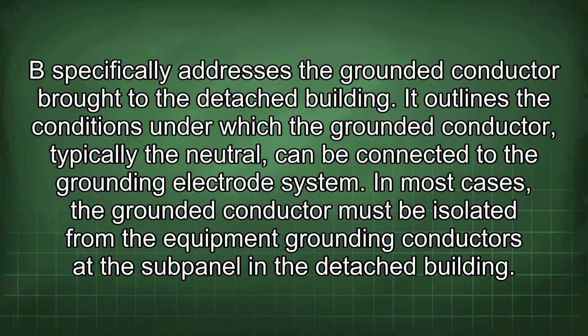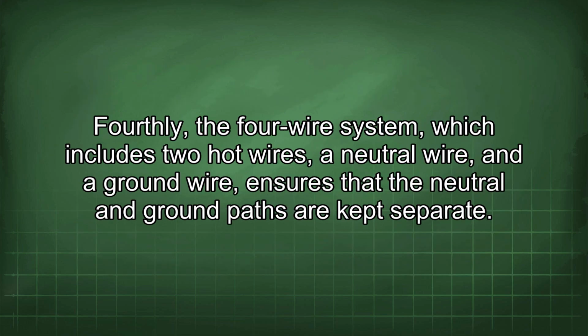Thirdly, NEC Section 250.32 B specifically addresses the grounded conductor brought to the detached building. It outlines the conditions under which the grounded conductor, typically the neutral, can be connected to the grounding electrode system. In most cases, the grounded conductor must be isolated from the equipment grounding conductors at the subpanel in a detached building. Fourthly, the 4-wire system, which includes 2 hot wires, a neutral wire, and a ground wire, ensures that the neutral and ground paths are kept separate.